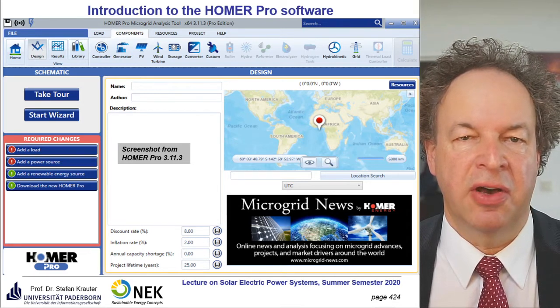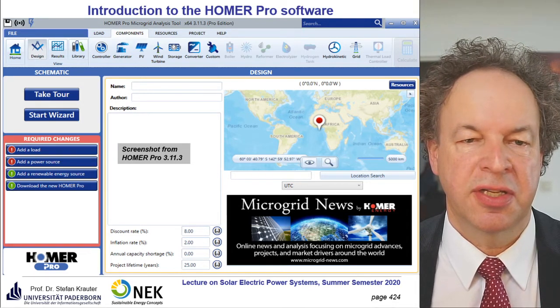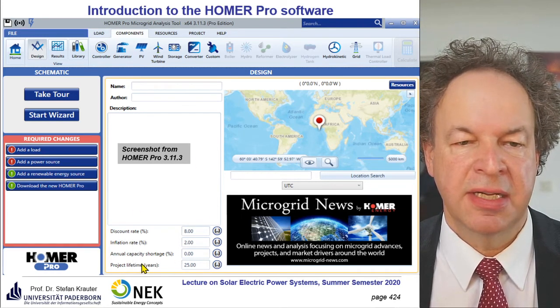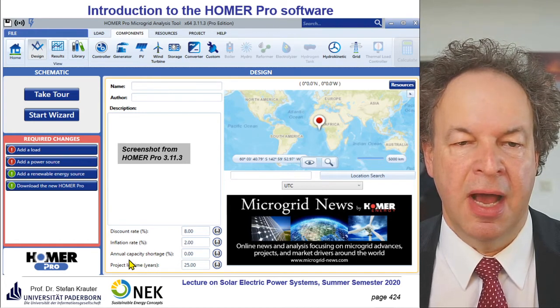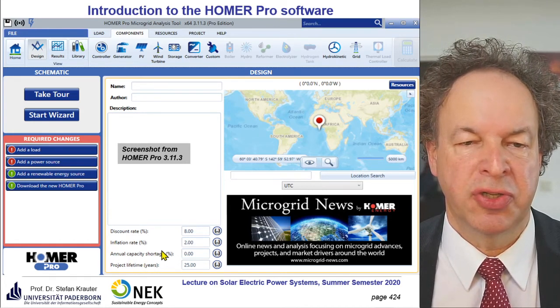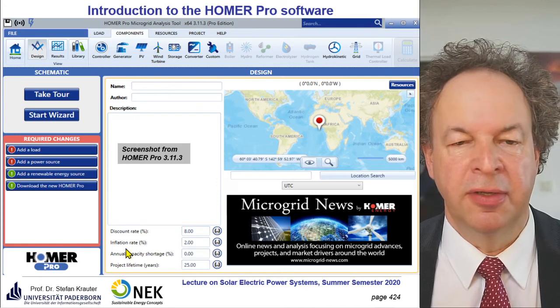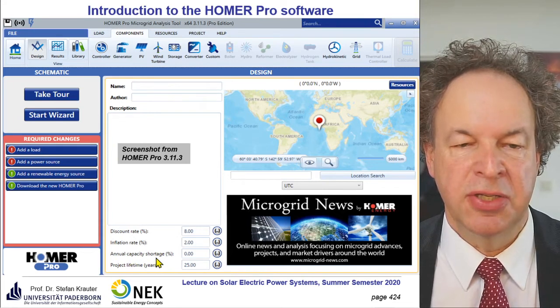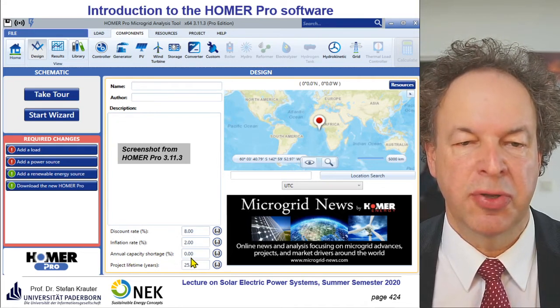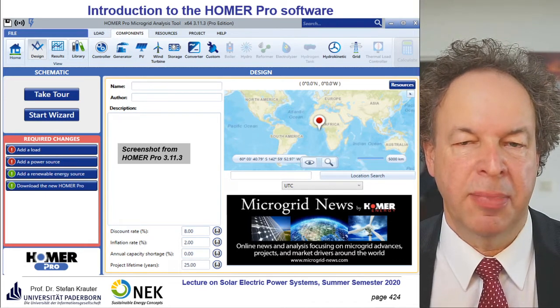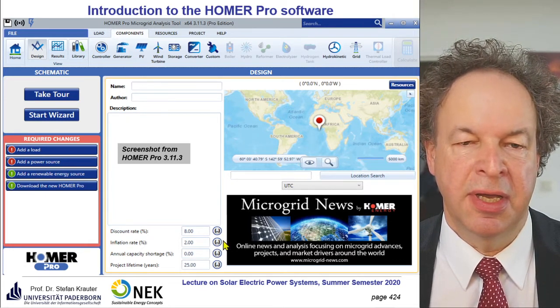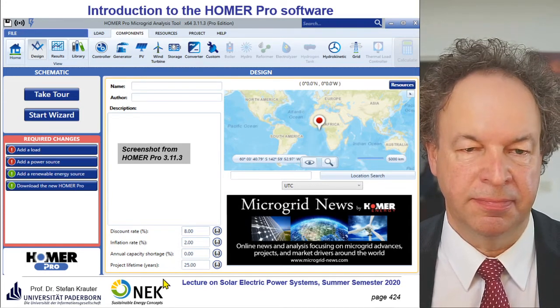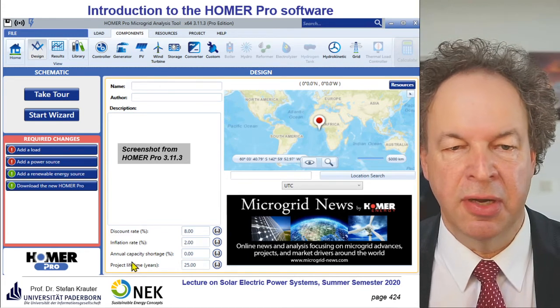The Homer software interface shows location, financial site parameters including discount rate and inflation rate, and the allowed capacity shortage. This can differ significantly: if you have a hospital, all equipment must work 100% — so 0% shortage is allowed — while for a water pump you can allow some shortages, which makes the system considerably cheaper. You can also enter the project lifetime, the load, power sources, and renewable energy sources.